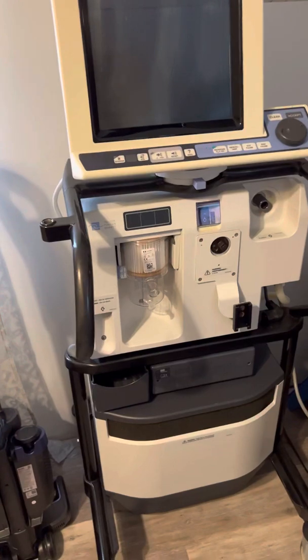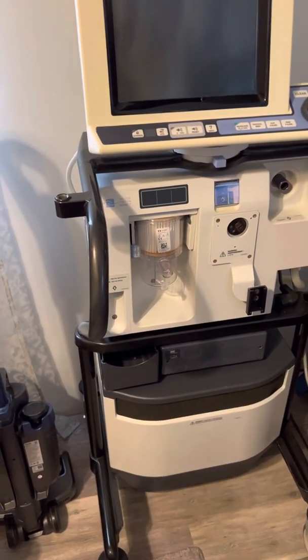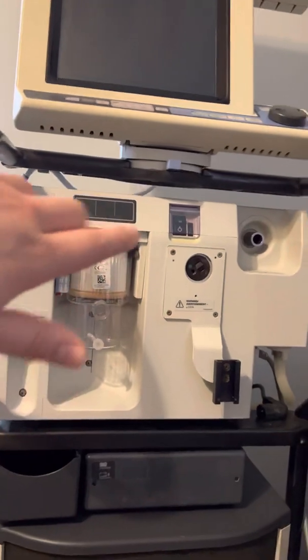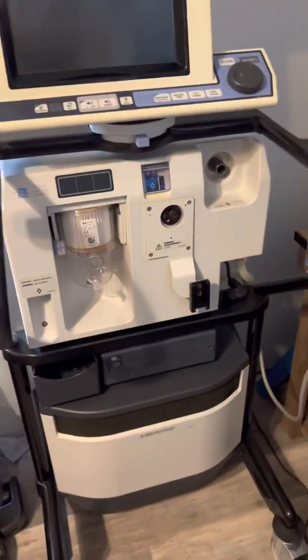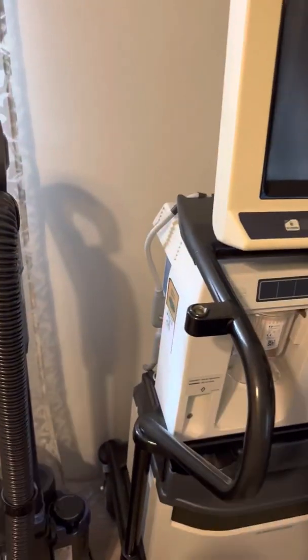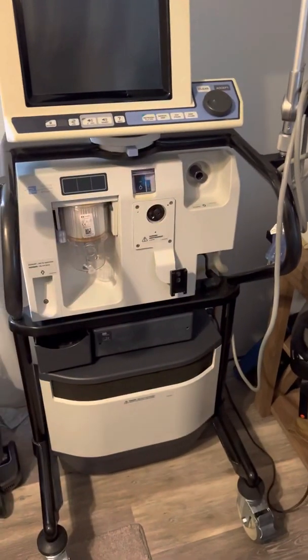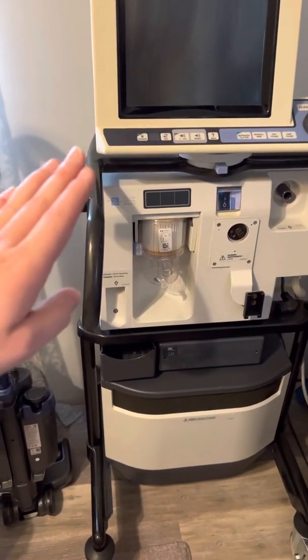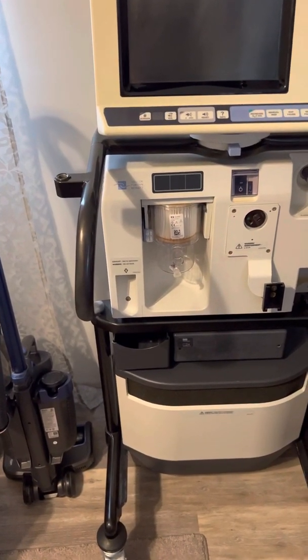This in here is the actual powerhouse of the vent — that is the ventilator itself. You can actually detach the screen; it's mounted to the stand and connected by a pigtail cord on the side of the ventilator. This is where your inspiration, your breath going to and from, would come back to the ventilator on this side. That's a heated expiratory filter that's viral and bacterial — it's a viral and bacterial filter.